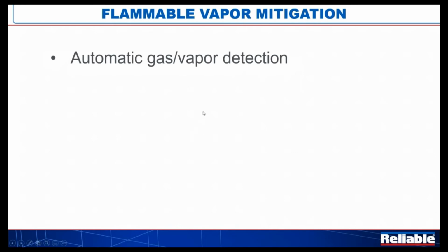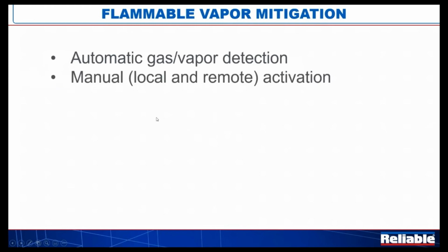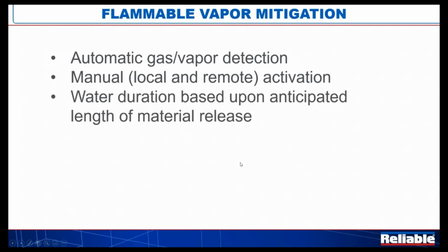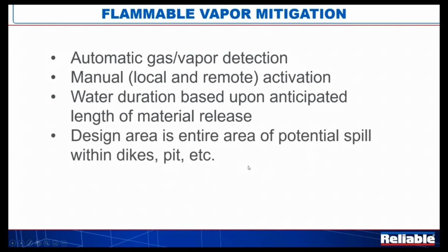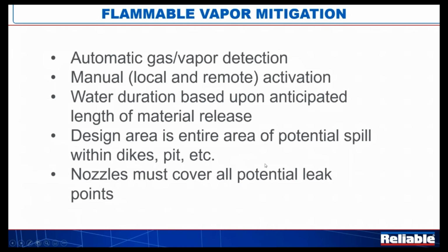We want to make sure that we have automatic gas and vapor detection. Kind of makes sense. We would probably have this in most cases with all of these systems: manual, local, and remote activation available to us. We want to analyze how long the material released might be and make sure our water duration is the same. We want to look at the individual areas, and perhaps for water supply reasons, it makes sense to cordon some areas off and make different systems. But again, we look at the protected area in terms of square footage, and that's our design area. And then if we have known leak points like valves or vents or things like that, we just need to look at those and have protection adequately applied to those areas.